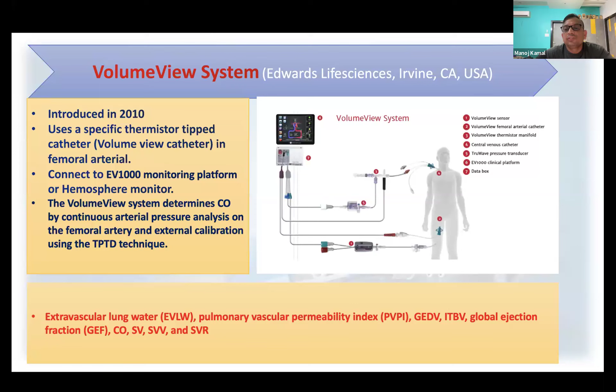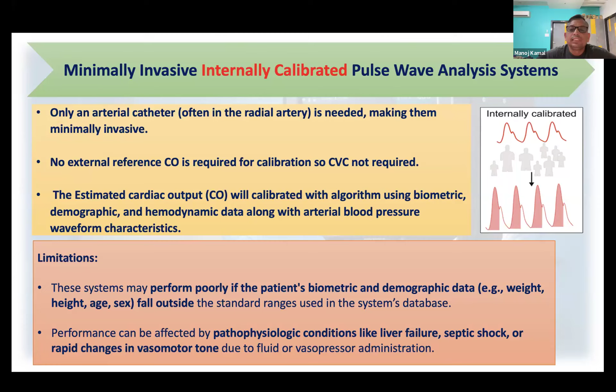Minimally invasive systems are further divided into internally calibrated or pulse wave algorithmic analysis systems, where there is no external reference cardiac output required for calibration. Only an arterial catheter is needed, making them minimally invasive, and the estimated cardiac output is calibrated with an algorithm using biometric, demographic, and hemodynamic data along with arterial pressure waveform characteristics. So performance can be affected by pathological conditions such as liver failure, septic shock, or rapid change in vasomotor tone due to fluid and vasopressor administration.